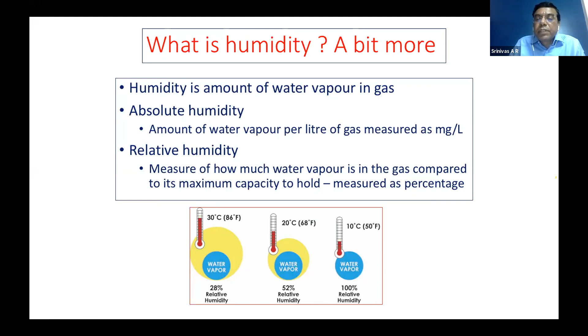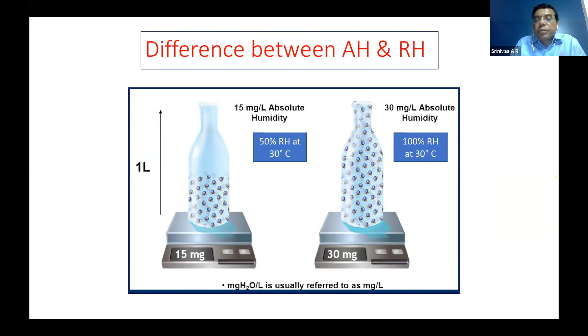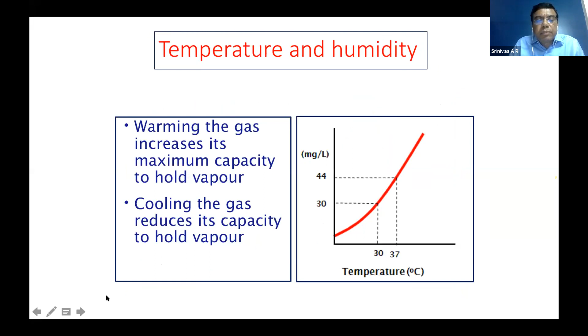So if you look at what is the difference. At 30 degrees centigrade, if you have 15 milligrams per liter of absolute humidity, this is 50% relative humidity, because this air can hold more water. But when you go up to 30 milligrams per liter of absolute humidity, this at 30 degrees gives 100% relative humidity. So as the temperature increases, the amount of water vapor the air can hold goes up. As the temperature drops, the amount of water it can hold significantly comes down. So warming the gas increases its maximum capacity to hold water vapor, and cooling the gas reduces its capacity to hold the vapor.